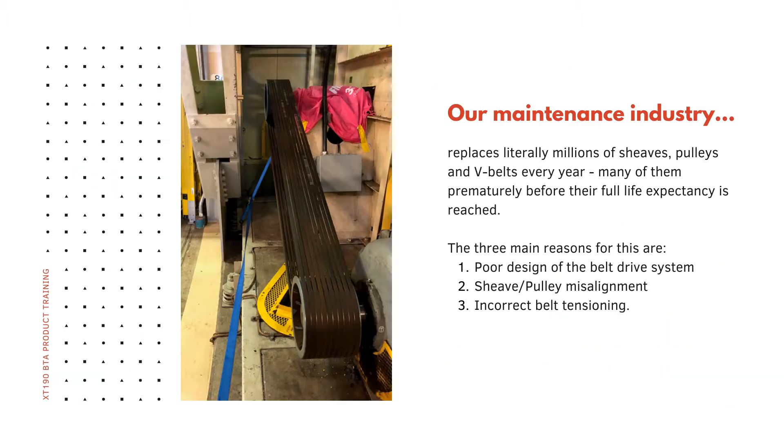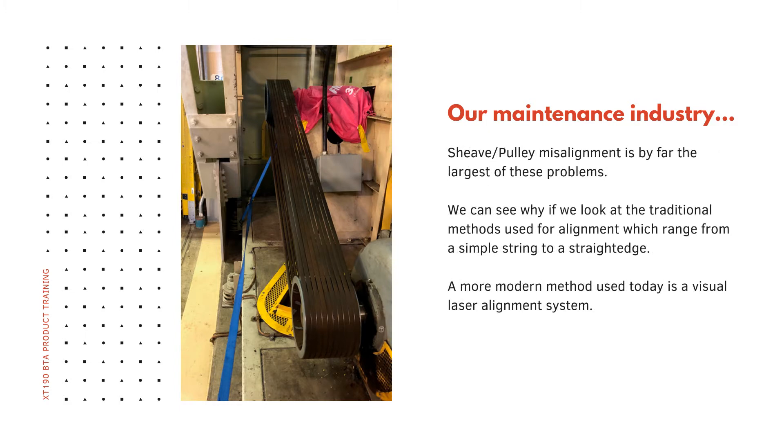Our maintenance industry replaces millions of sheaves, pulleys and V-belts every year, many of them prematurely before their full life expectancy is actually reached. The three main reasons for this are poor design of the belt drive system, sheave and pulley misalignment, and incorrect belt tensioning. Shiv and pulley misalignment is by far the largest of these problems.